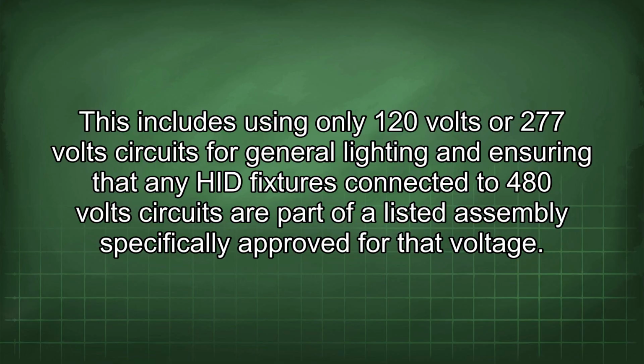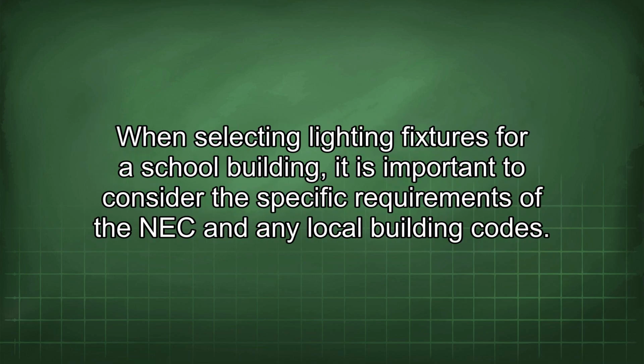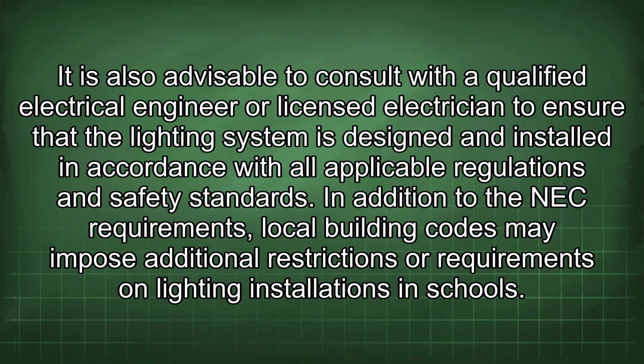This includes using only 120-volt or 277-volt circuits for general lighting and ensuring that any HID fixtures connected to 480-volt circuits are part of a listed assembly specifically approved for that voltage. When selecting lighting fixtures for a school building, it is important to consider the specific requirements of the NEC and any local building codes. It is also advisable to consult with a qualified electrical engineer or licensed electrician to ensure that the lighting system is designed and installed in accordance with all applicable regulations and safety standards.